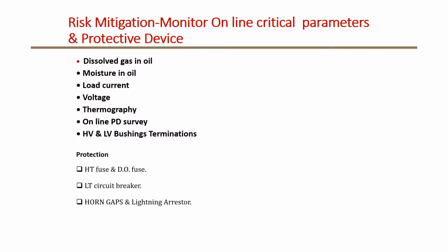The problem with distribution transformers is that you won't get an outage. Utilities run them in a manner where they install it and let it run to failure, with no space in between. So at least we do some online inspection and data recording to save these transformers. Some gadgets could help too, like HT fuse or DO fuse for protection on the HT side, LT circuit breakers for protection on the LT side against any fault, and horn gap and lightning arrestor.